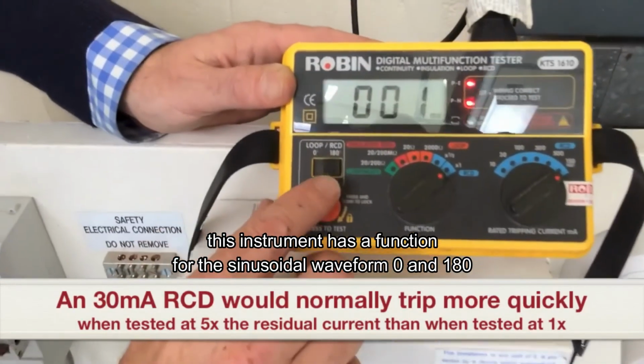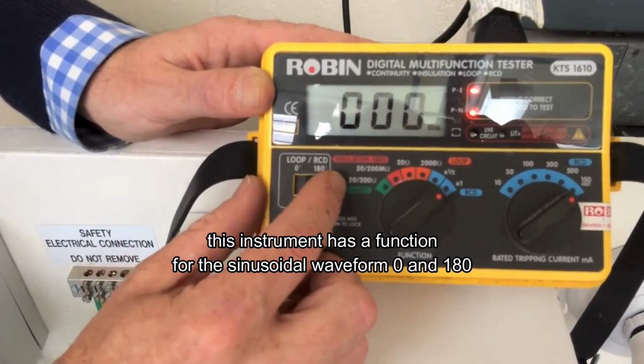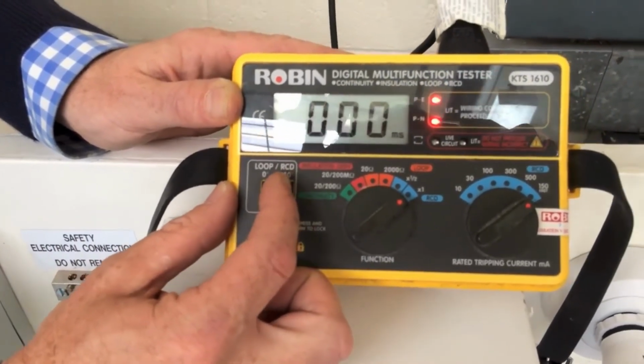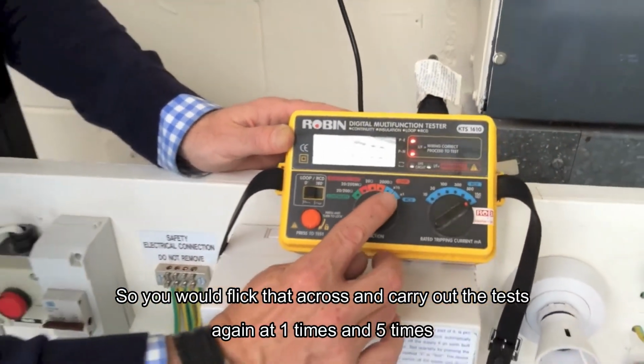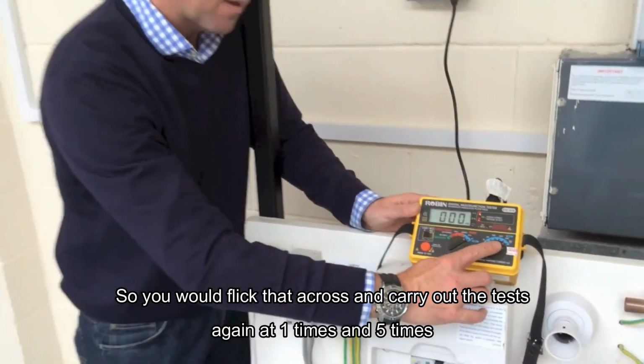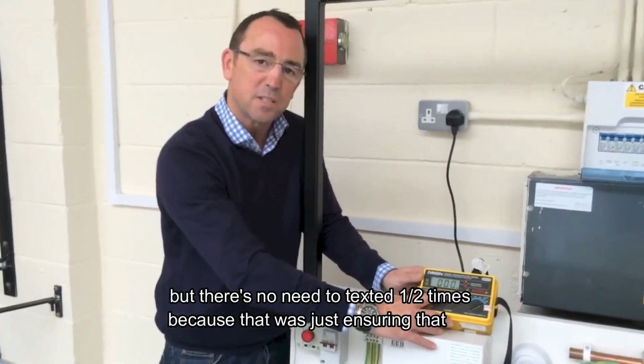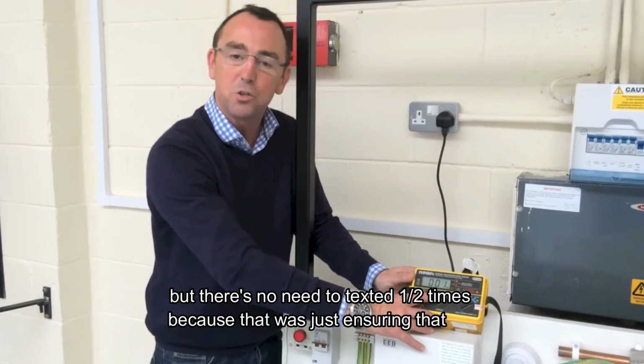This instrument has a function for the sinusoidal waveform 0 and 180. So you would flick that across and carry out the test again at 1 times and 5 times. But there's no need to test half times because that was just ensuring the nuisance tripping doesn't take place.